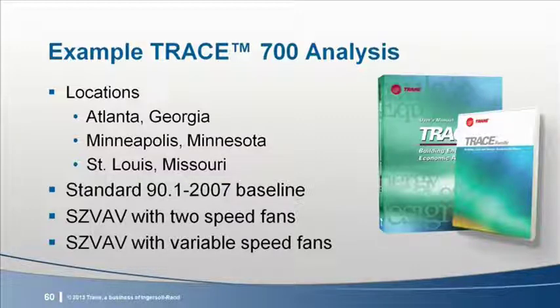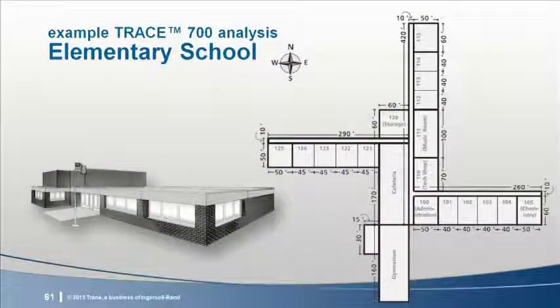We then changed the airside system to a SingleZone VAV and made incremental changes. First, 2-speed fans were used, and finally, variable speed drives were used. We did not alter the envelope or internal loads. The only changes from alternative to alternative are within the airside systems. The simulated elementary school is a single-story building and suitable for rooftop units.